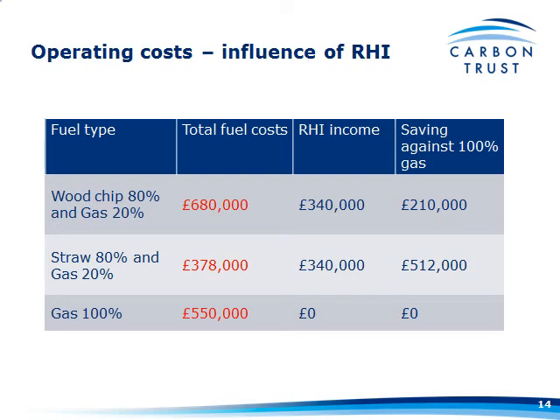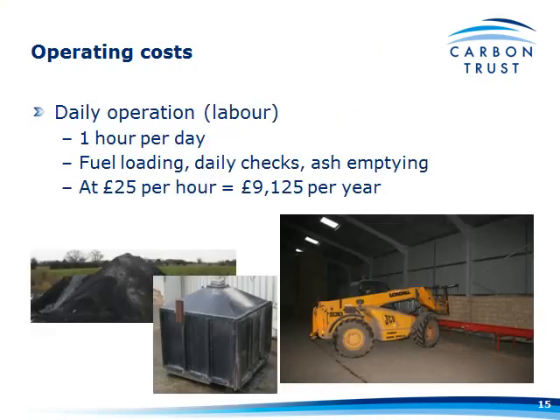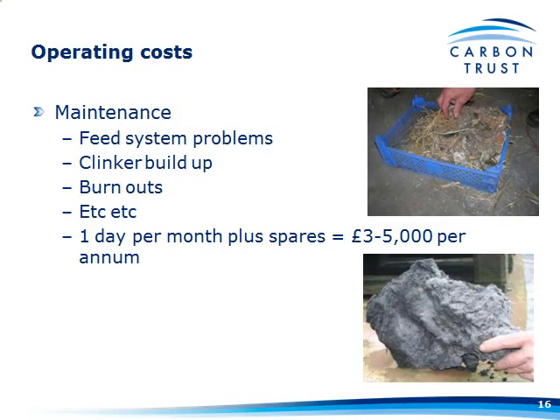The other things you mustn't forget, and they are quite large costs: daily operation — let's say it's an hour a day, which seems fairly typical from speaking to people who've installed systems. That includes fuel loading, daily checks, de-ashing, and so on. You're going to need a guy with a telehandler if you're loading Hesston bales into a conveyor. At £25 an hour, that's nearly £10,000 a year you've got to add to your operating costs over and above a gas system.